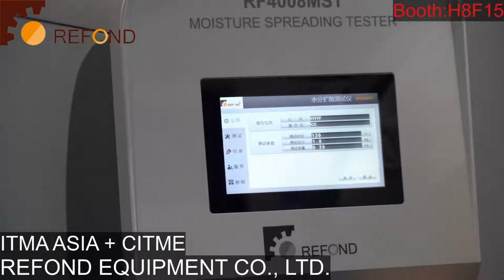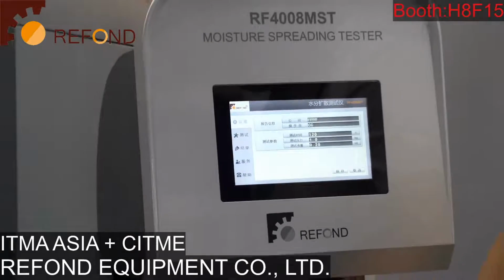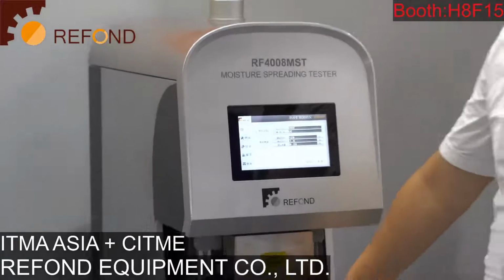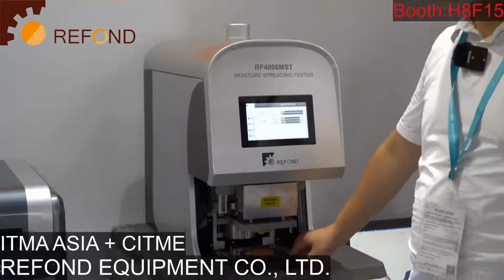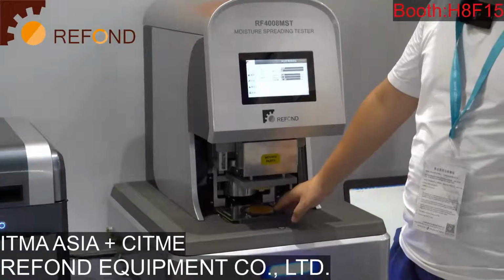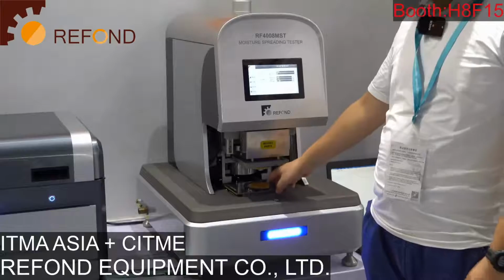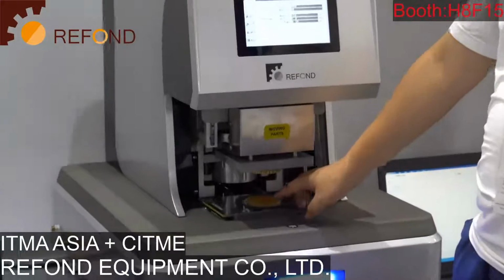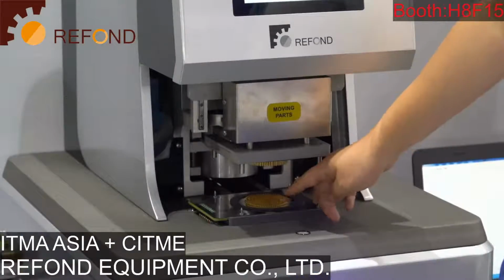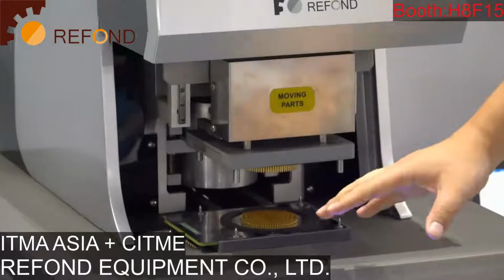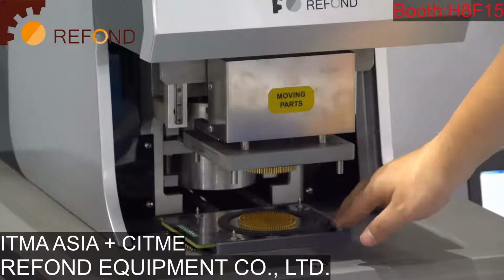In this machine, as per the standard, we have these test probes that will make contact with the specimen on both sides, the top side and the bottom side. And this test probe will measure the resistance distribution across the surface of the specimen.